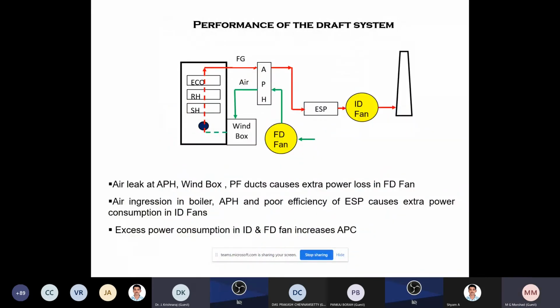Now, the draft system. The FD fan sucks the air from the atmosphere. Then it goes to the air heater and heats up. The heated air goes to the wind box. From the wind box it is distributed, becomes flue gas, and goes back through the ESP and chimney. So this is the air circuit.